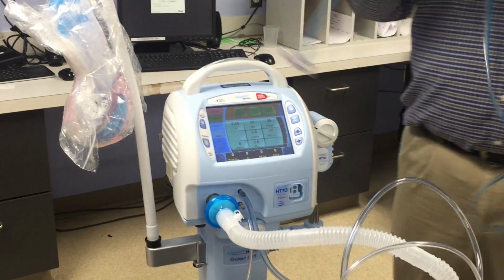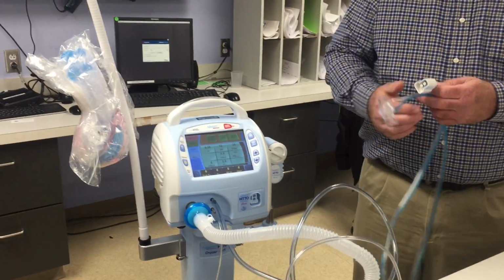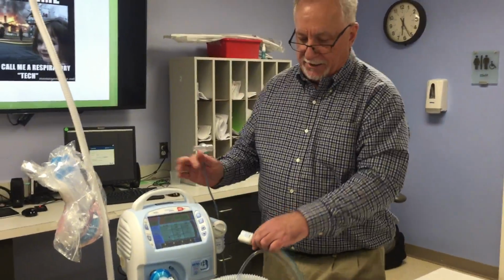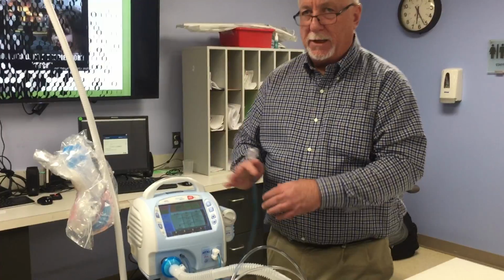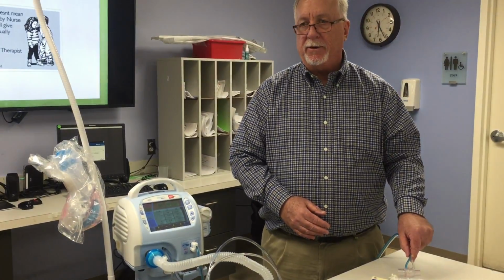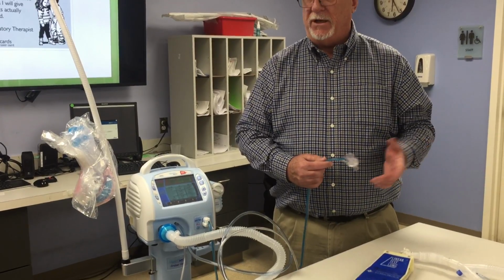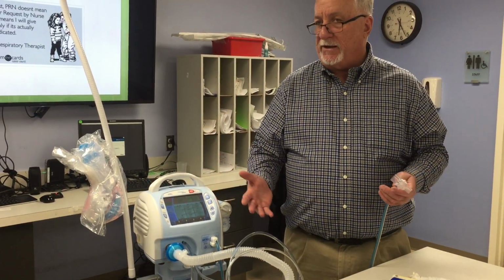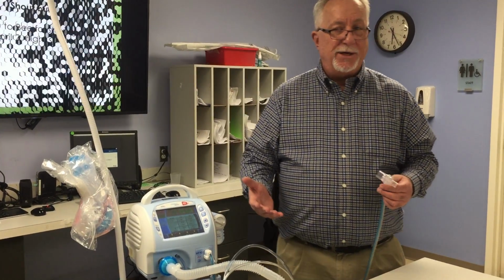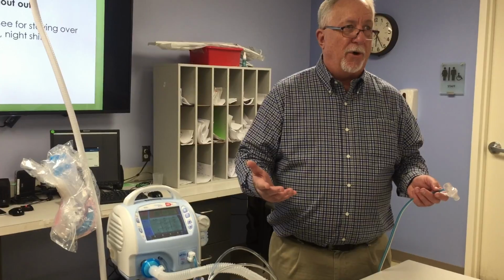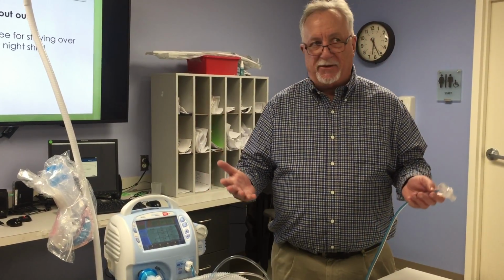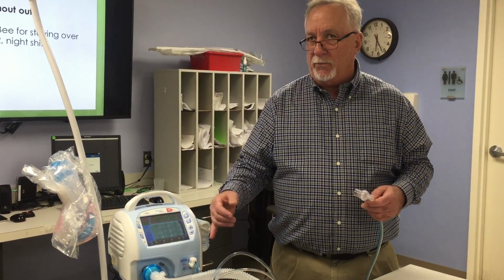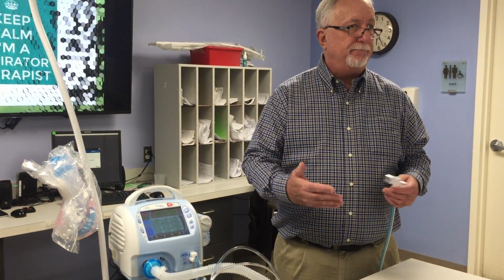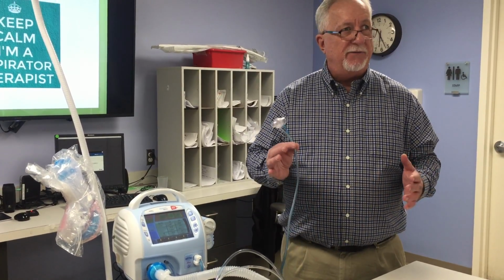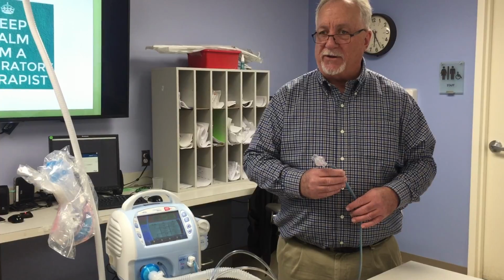The other thing this ventilator has over here is a flow sensor, and it hooks on in line. It just pushes in. You add it to your system here, and what it'll do is give you exhale volumes. It'll give you flow volume loops, those types of things as well. In an emergency preparedness situation, you're probably not worried about flow volume loops, but maybe exhale tidal volumes, yes or no. But it will give you an inspiratory tidal volume that goes to the patient. So you can decide if you want to use that or not. It just gives you that much flexibility.